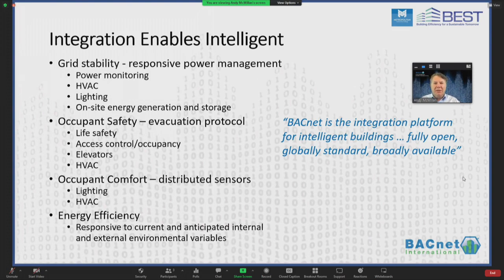Some benefits of more intelligent strategies include enhancing grid stability. When a building can be responsive to what the grid needs, it can help beyond its own needs—helping the larger grid by reducing power when the grid is peaking, providing on-site generation, or using on-site storage to take excess power from the grid. But all of those things require integration in the building: power monitoring, HVAC, lighting, and on-site generation and storage all need to communicate together if they're going to do that effectively. So integration is what enables that intelligence.